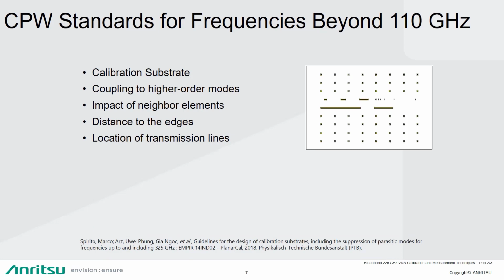So now we can start to look a little bit closer at the actual calibration standards that are located on calibration substrates. And when designing the coplanar calibration standards for millimeter wave frequencies, it's important to minimize possible coupling of the electromagnetic energy into the higher order propagation modes that can be supported by the calibration structures or the calibration substrate.